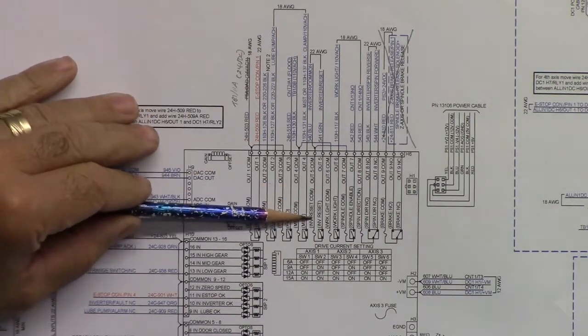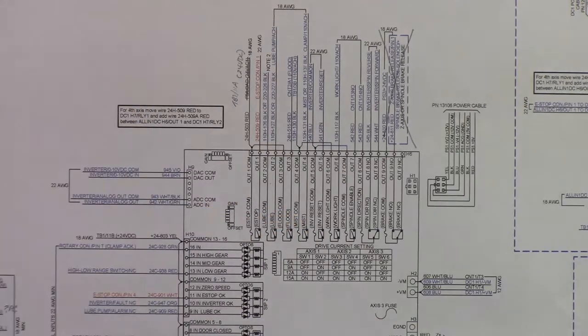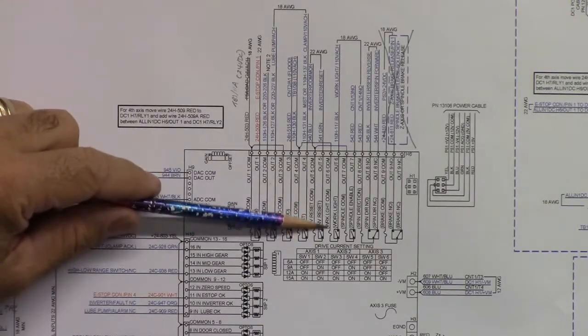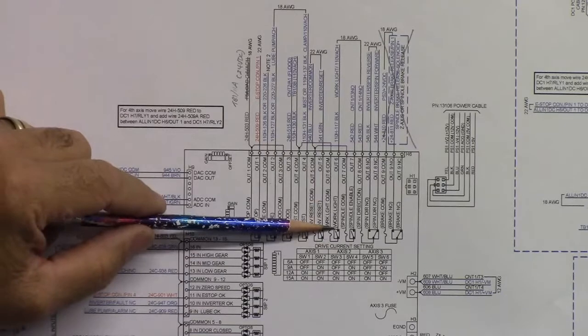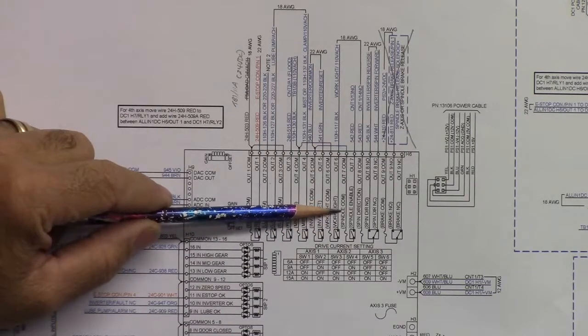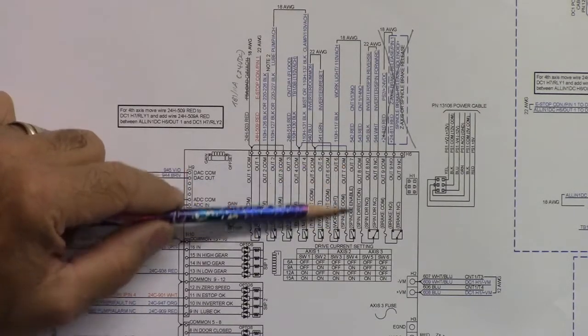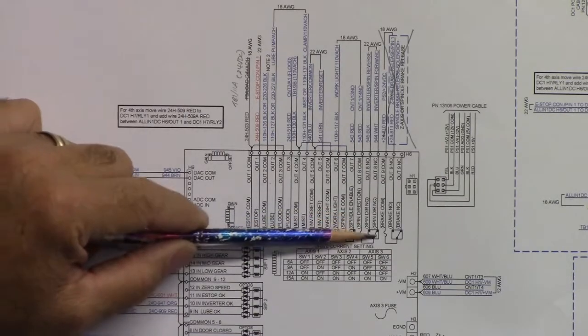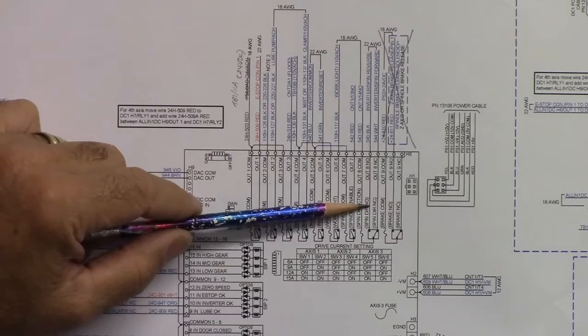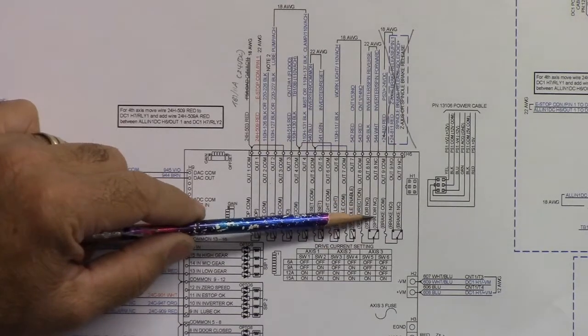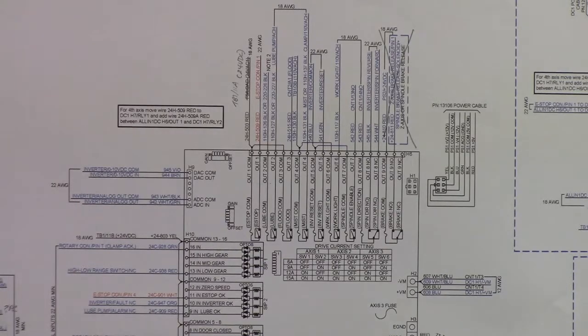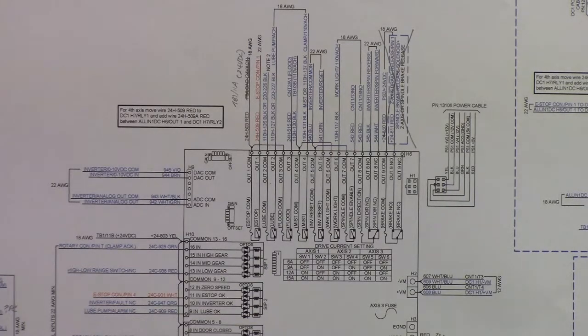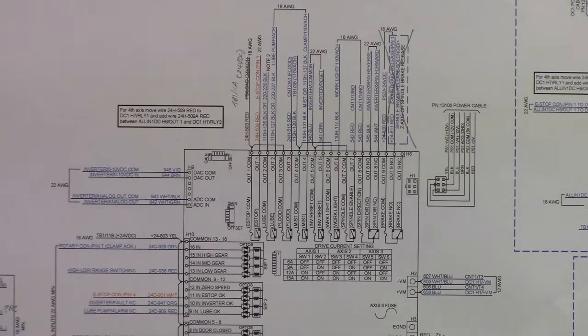The next one here is inverter reset. That's the VFD reset. So if there's a fault and you reset, it'll reset the VFD for you. The next one here is a work light. So your work light can run through this, no problem. The next one is spindle enable. So this is output seven is spindle enable. And then the next one is spindle direction. This is where we're using that single pole double throw. In one direction, we're going spindle forward. And when that relay goes the other way, it goes into spindle reverse. The last one is a spindle brake. That's the one that they happen to have assigned to output nine. If you have a large spindle brake, it's definitely got plenty of fuse and contact there to control it.